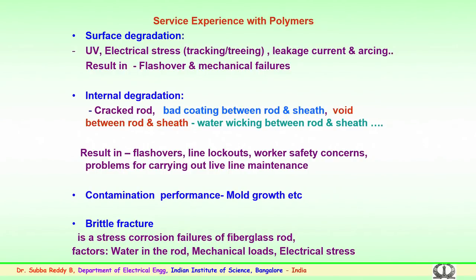Some reports have indicated mechanical failures because of degradation. Similarly, internal degradation could happen because of a cracked rod, as I mentioned, in the manufacturing stage or during stringing, when there could be internal damage. Because of the end fittings with the pressure, micro cracks could have formed, and these could develop over a period of time. Or it could be because of the coating between the rod and sheath before the silicone rubber material is molded on the fiberglass rod.